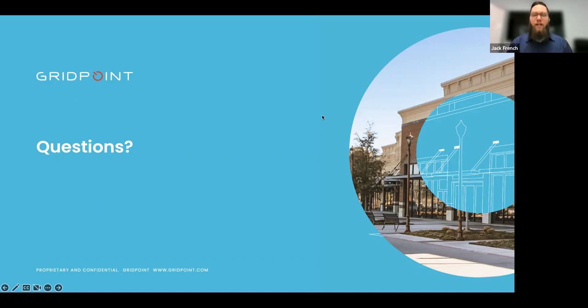So enrolling in things like demand response programs, which we talked about, is a great way to limit your demand. And of course, we have the load curtailment algorithm, which is not exactly, but kind of similar to real-time demand response. Those events are triggered by the controller, and the algorithm uses machine learning to figure out: is my next peak going to reach 95% of my peak in the last 7 days? If it is, then I need to curtail HVACs and allow them to drift so that I don't increase the severity of my next peak. So, really good question, but a lot of things to unpack there.